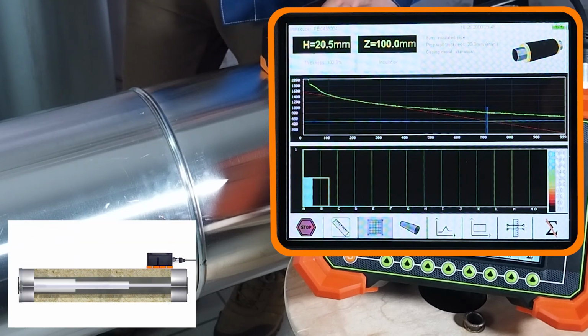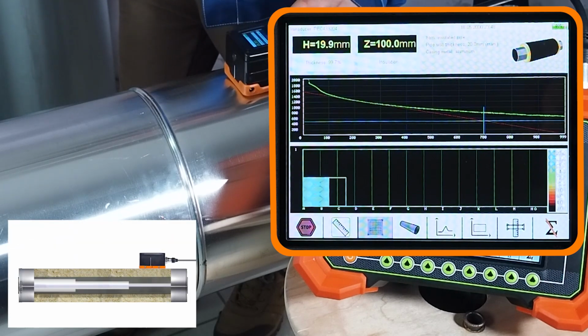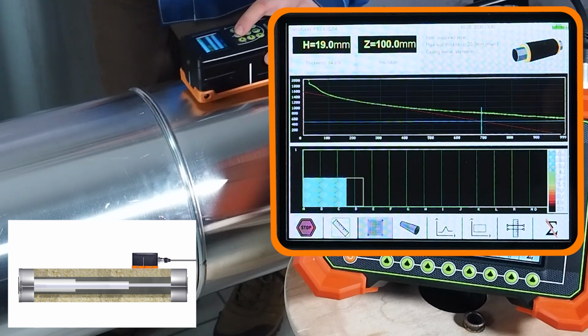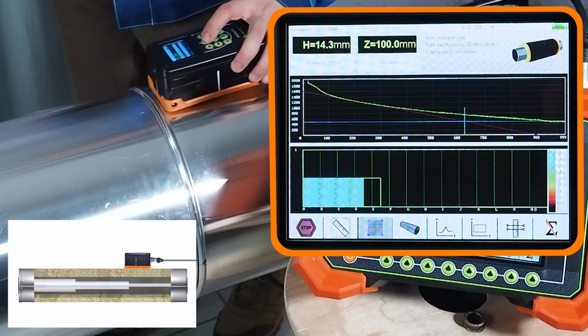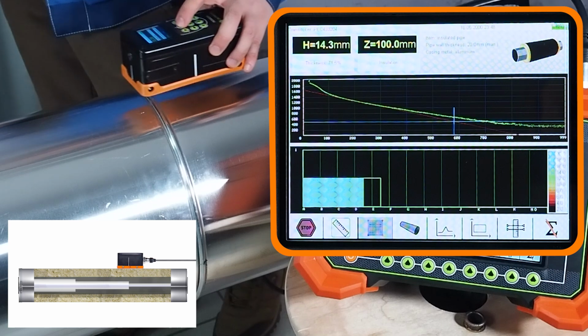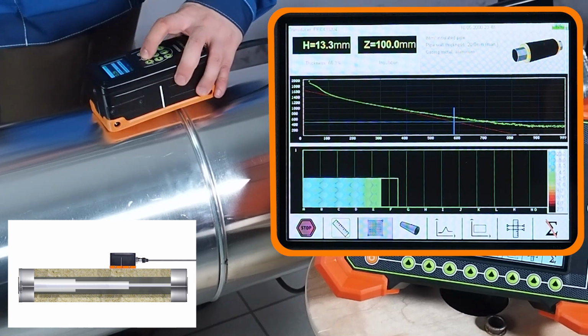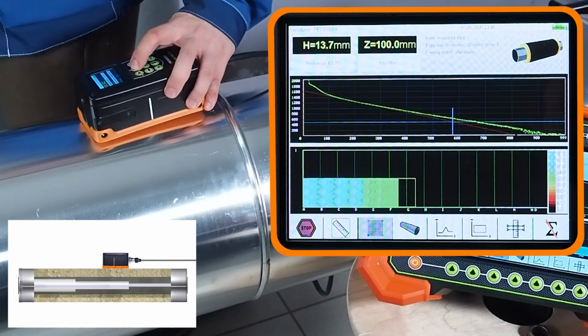Let's check whether the device can sense the 3 sections with different wall thicknesses and correctly measure the wall thickness along the entire pipe length. We do not start measuring from the very edge, since the measurement method has edge effects that can negatively affect the results.